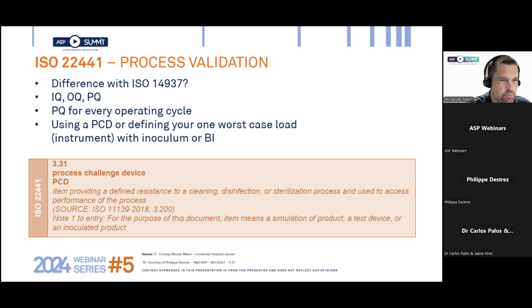And of course, what's really important, what's changed, is that the PQ is for every operating cycle. So if you have a hydrogen peroxide sterilizer with more than one program, you need to make sure that for every program, you perform that performance qualification. And using a PCD or defining the worst case load, I think that's the most difficult one. That was already a challenge in steam sterilization processes, but in this case, you also need to look at every device you are reprocessing in the vaporized hydrogen peroxide process.